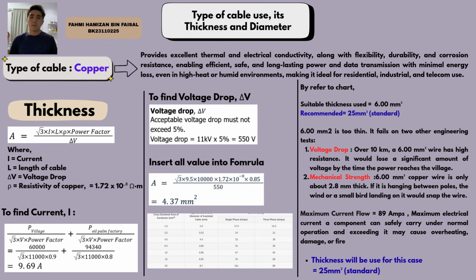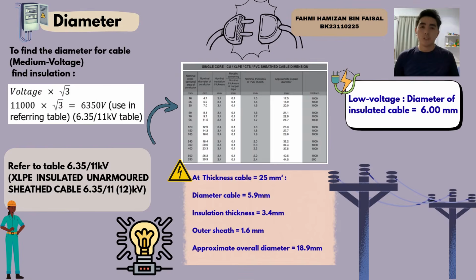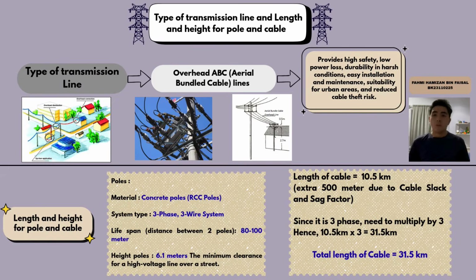Although 6 mm squared meets the basic calculation, it is not suitable due to high voltage drop and poor mechanical strength. Therefore, a standard 25 mm square cable is selected. For medium voltage, by referring to the table for 6.35/11 kV insulation, it is shown that the overall cable diameter is about 18.9 millimeters.